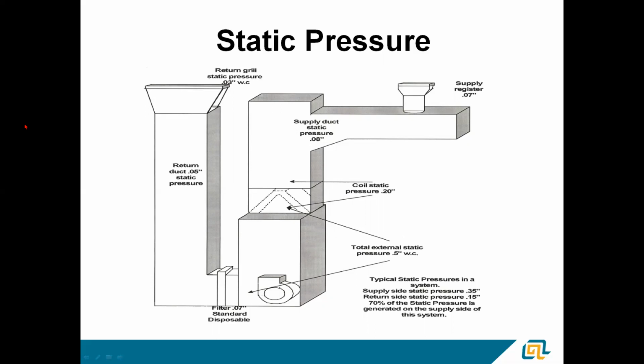Something that I find interesting on this too is a filter should have about a 0.07 inch drop for a disposable filter. We all know that everybody loves using those pleated filters. If you measure the drop across some of those things, it gets to be close to 0.3 inches. So with a pleated filter in there, it takes up most of the static pressure that's in the system. I tell people that the duct systems are honestly designed around those leaf catcher filters. They work great, change them once a month, but be cautious if you start seeing the heavy pleated filters, because they're really restricted to airflow.